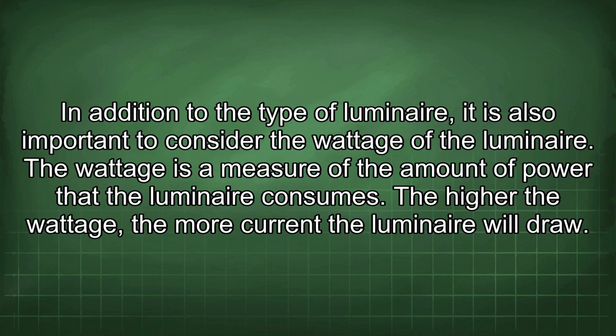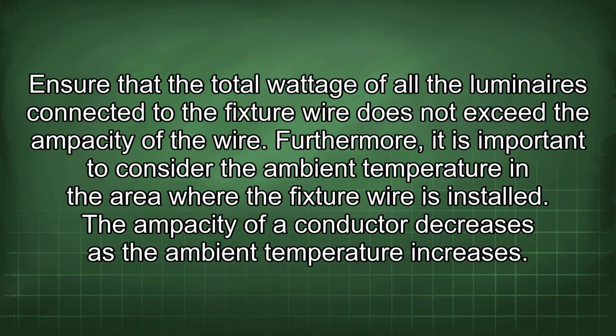In addition to the type of luminaire, it is also important to consider the wattage of the luminaire. The wattage is a measure of the amount of power that the luminaire consumes. The higher the wattage, the more current the luminaire will draw. Ensure that the total wattage of all the luminaires connected to the fixture wire does not exceed the ampacity of the wire.